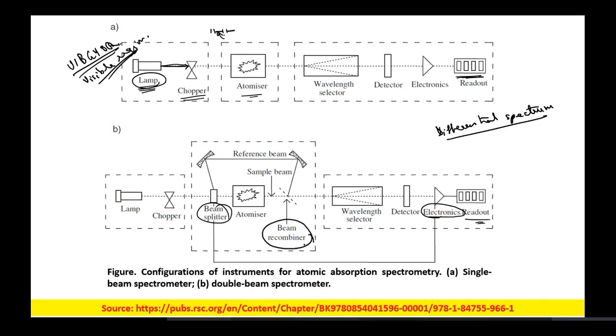There is a beam recombiner. Its job is combining the beam from the sample and from the reference. When the sample beam is going through the beam recombiner, the reference beam is not available and vice versa. When the reference beam is sent to the detector, the sample beam does not gain entry into the detector.